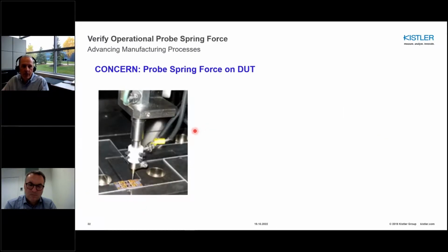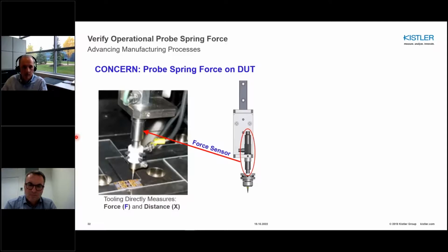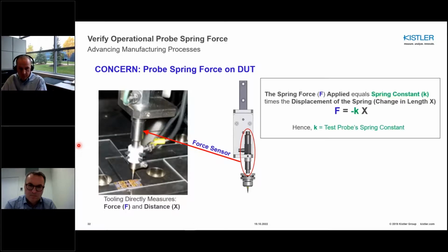In this illustration, we're showing the tooling. The tooling actually directly measures force and displacement. That's the force sensor right there. From physics, or more specifically from Hooke's law, we know that if an object applies a force to a spring, then the spring pushes back with an equal and opposite force onto the object. Hence, the force a spring probe exerts on an object, or in this case, the micro bump, is simply stated as F equals minus Kx.